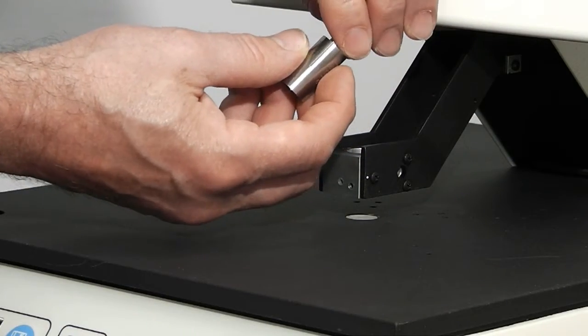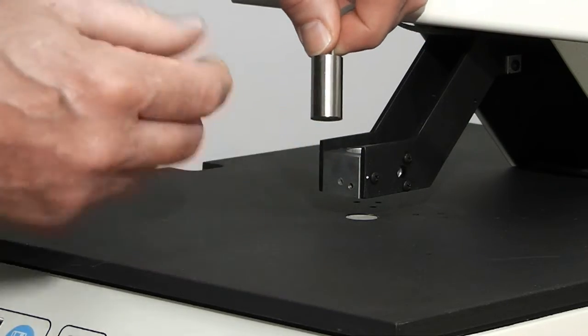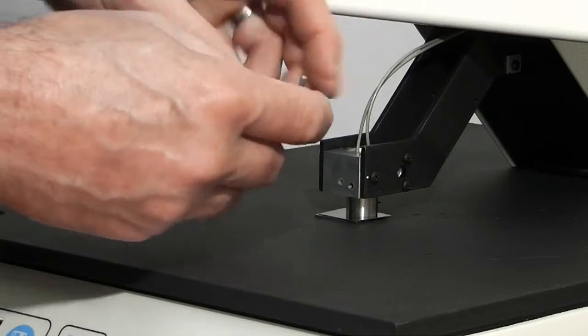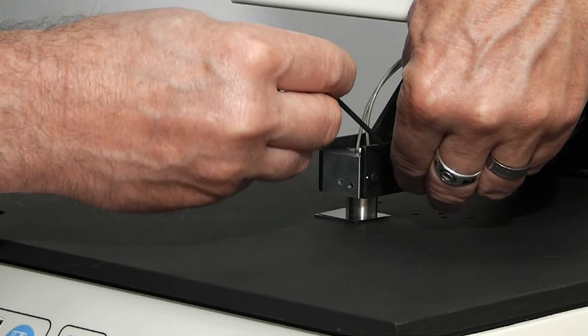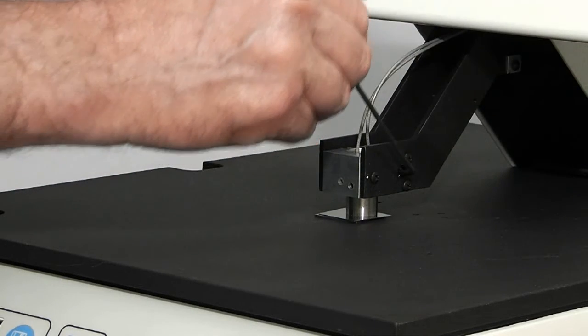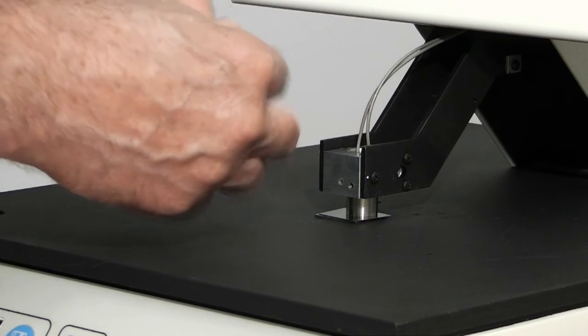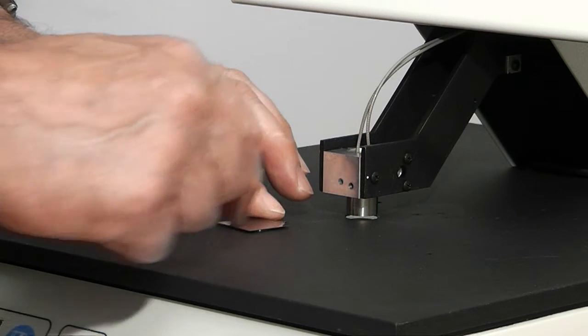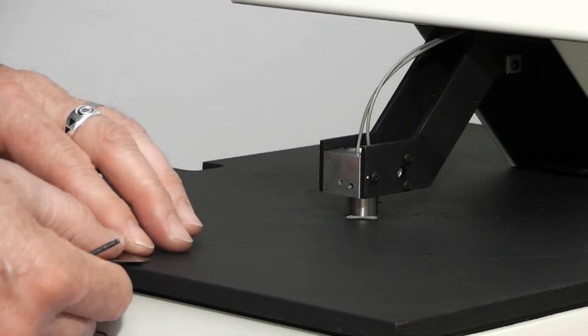There's a Phillips screw, and then we'll use an Allen wrench, and what we're going to do is we're going to rotate the probe 180 degrees, and you have to do that carefully so you don't break the wires. Once you've done that, you're going to gap the probes, and one of the ways we gap the probe, we set it back up for 1.2 millimeters, and you can use a gauge block to do that, something where you can slide in there. You bring your probe down so it's touching, and then you start to tighten it up. You pull out your gauge block or whatever you have to set your height, and then finish tightening this up and put the nose piece back on, and then we'll come back and we'll do a calibration of the system for gallium arsenide.